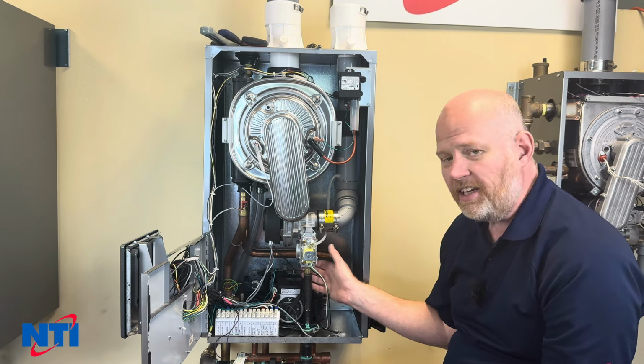Keep in mind that no matter what, you're going to get a small amount of water come out of here. It should just drip into the cabinet, not do any harm. However, you may want to put some paper towel around the electrical connections and just watch out for anything that might be below the boiler that could get dripped on. So that's our first screw out.